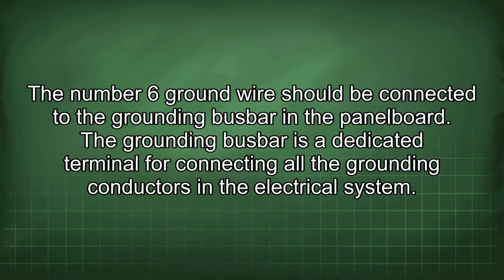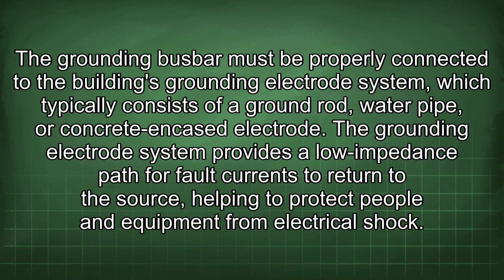The number 6 ground wire should be connected to the grounding busbar in the panel board. The grounding busbar is a dedicated terminal for connecting all the grounding conductors in the electrical system. The grounding busbar must be properly connected to the building's grounding electrode system, which typically consists of a ground rod, water pipe, or concrete-encased electrode. The grounding electrode system provides a low impedance path for fault currents to return to the source, helping to protect people and equipment from electrical shock.